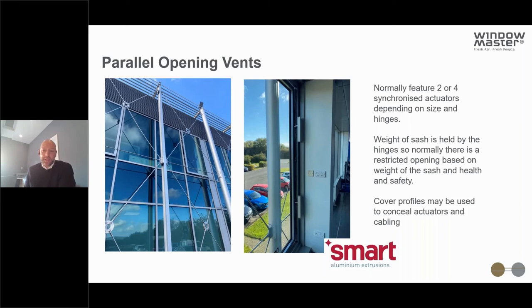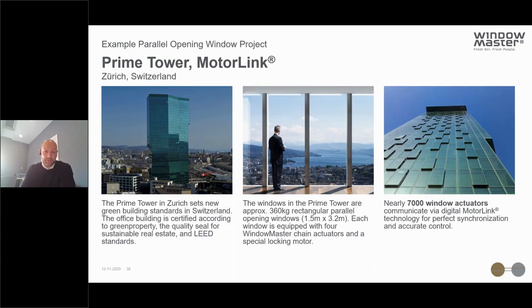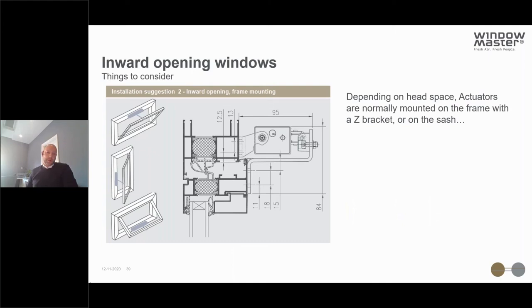Parallel opening vents have become a new trend in recent years. They normally feature two or four fully synchronised actuators depending on the window size. The majority of the vent weight is held on the hinges, so the actuators control movement and overcome friction. Cover profiles can be used to conceal actuators and cabling. We were involved with a large Schüco project a few years ago with nearly 7,000 actuators controlling a good number of parallel opening vents. We can also automate inward opening windows. There are two ways of mounting the actuators — if there's head space, they can be fitted on the frame with a Z bracket, or if not, mounted on the sash with extra consideration needed for cable routes around the outside.